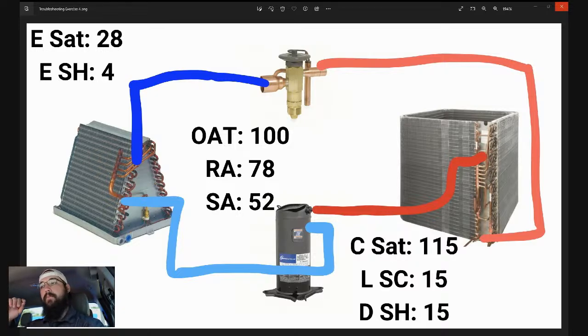So if that was part of your question, well, maybe that's why I can't get my system to look right, because I'm not pumping properly. You're moving refrigerant here. You can tell, if you were not moving refrigerant properly, you'd have high saturations, you'd have high superheats, you'd have low condenser saturations, your subcooling would be off, you'd have very different readings, and your discharge superheat wouldn't be so low. So an inefficient compressor is going to run wild with discharge superheat. In this particular case, if anything, we've got a fairly low discharge superheat at only 15 degrees.